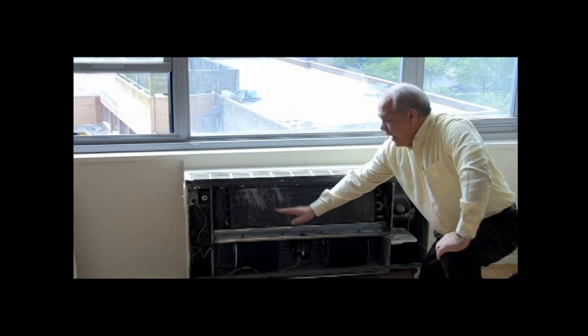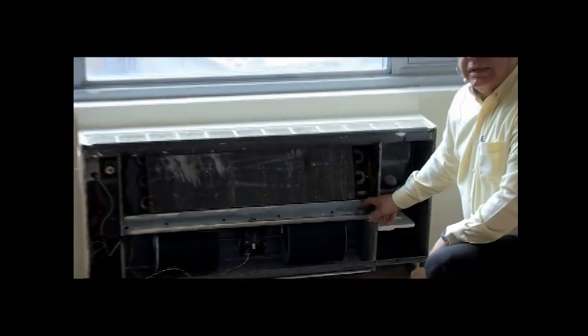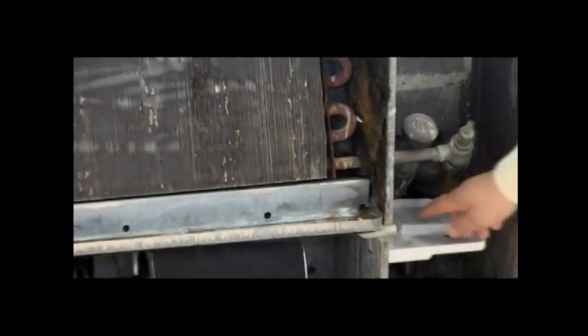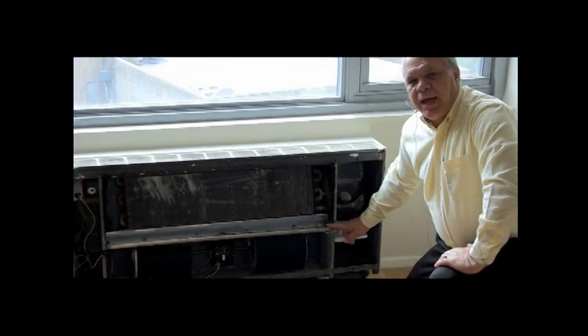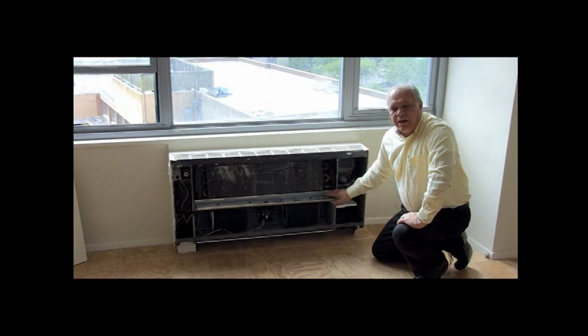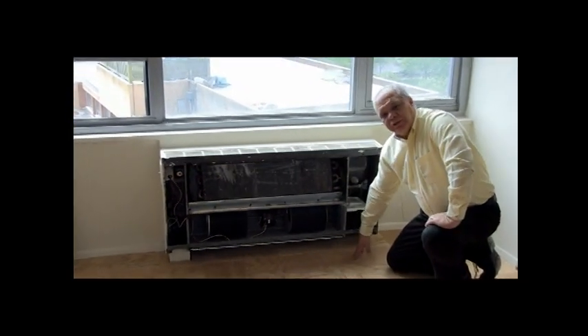The system itself has to be clean to keep any debris from going down the drain. There's a small drain here and a second drain here — these would be the only reasons you would have a convector leak. If either of these two drains clog at any time, you'll have a problem with water overflowing and damaging your floor.